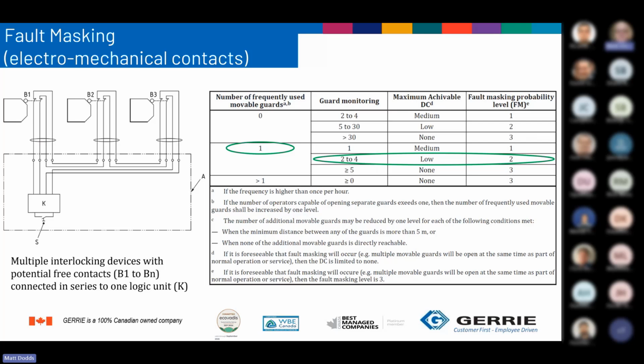So when performing safety calculations, fault masking must be taken into consideration. For example, if you have one frequently opened door guard in series with another three guards, the maximum achievable diagnostic coverage is low. However, if you add one more guard, you now have no diagnostic coverage. So again, these are all factors when referring to ISO 13849 for calculating the performance level of your circuit.